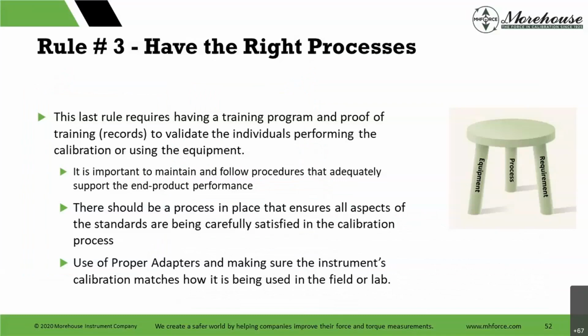The last rule requires having a training program and proof of training records to validate that an individual is performing the calibration or using the equipment. It is important to maintain and follow procedures that adequately support the end performance. There should be a process in place that ensures all aspects of the standards are being carefully satisfied in the calibration process. Use of proper adapters. We talked about that a little bit last week. It's so important for mechanical instrumentation. You get it some with electrical and test leads and other things, but really when you're talking about mechanical interaction, a soft material is going to produce mostly less output than a harder material. So adapters, orientation, alignment, all very, very important when it comes to force measurement.